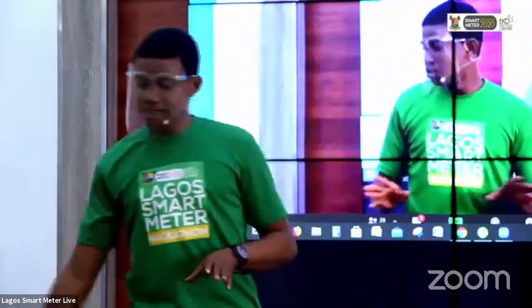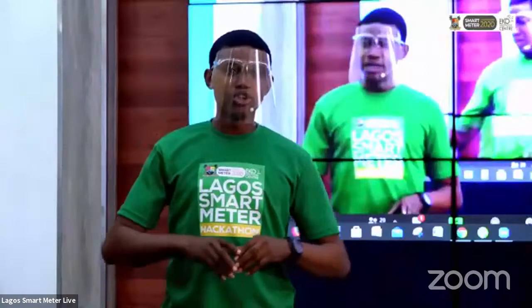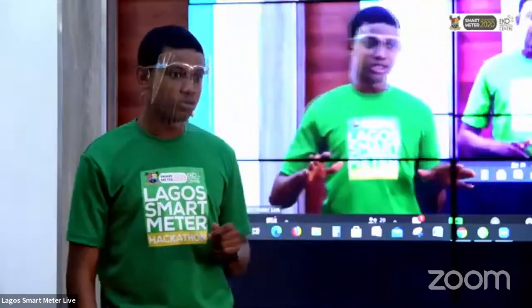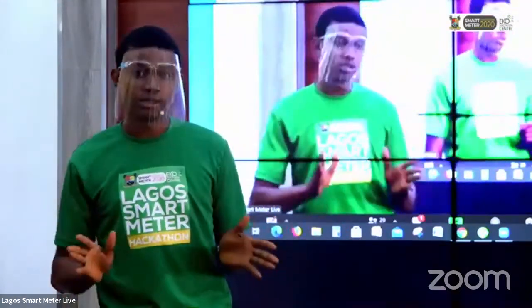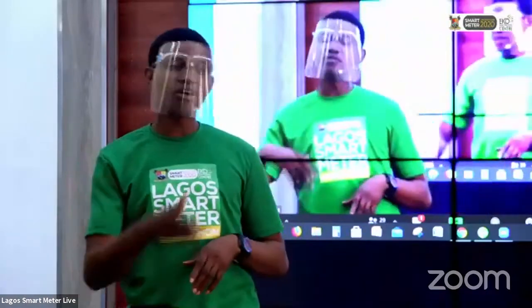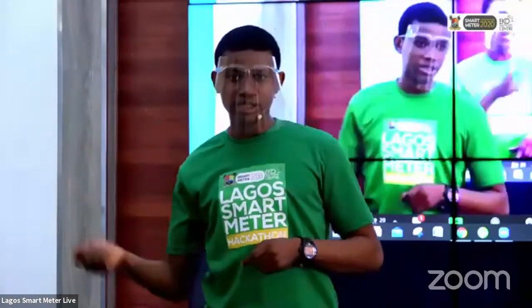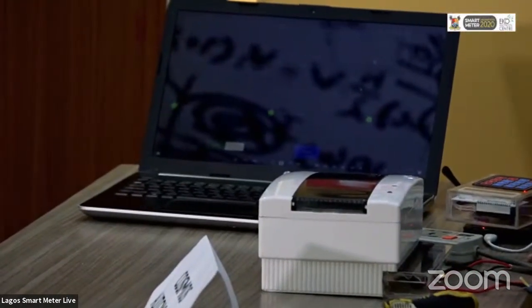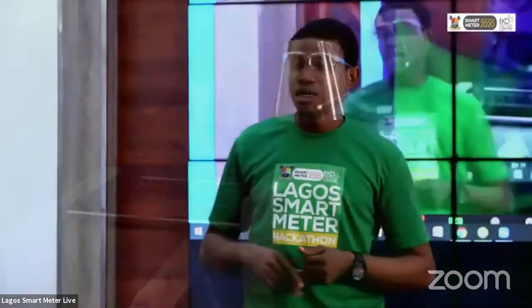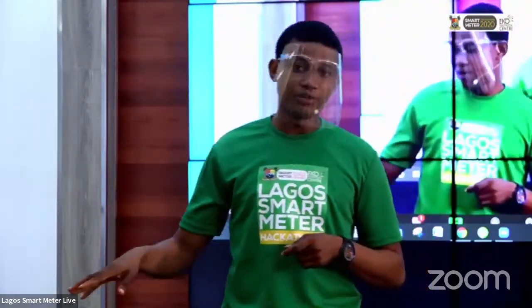Apart from that, an energy meter normally has one thing in common: monitoring of energy. So apart from the standards, the monitoring system now has to deal with your current reading and your voltage reading. We used current transformers of the ratio 2,500 by 1, and an ADC, the ADS1115, which is a 16-bit ADC, to measure our current and voltage.